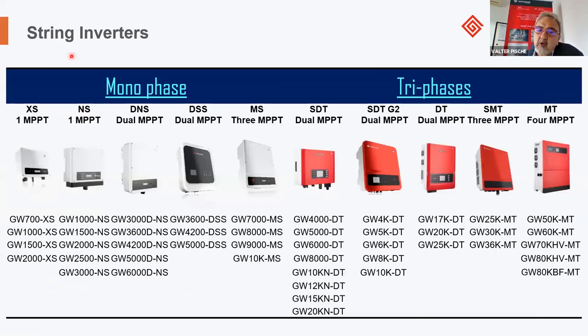You can see here a summary of all the products for what we call the string inverters. We have the monophase and the three phases. For the monophase, we have the champion in terms of compact size, which is our XS product, ranging from 700 watts up to 3 kilowatts. And this front size is just the size of an A4. You can imagine, in an A4 like this, for a depth like this, you have a device capable of driving between 700 watts and 3 kilowatts of photovoltaic modules. This is, I think, a record among inverter producers, and it's really a remarkable result.